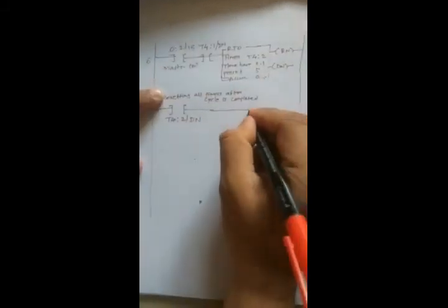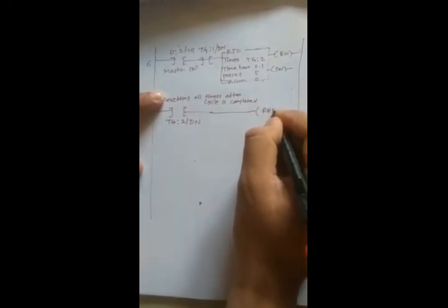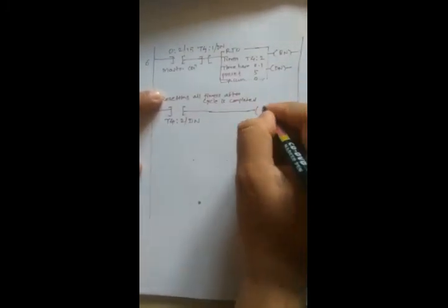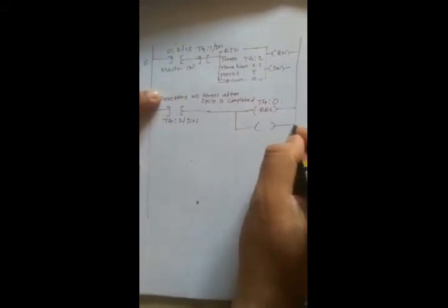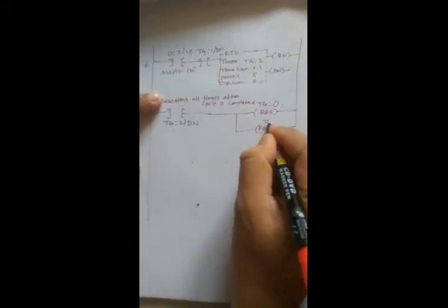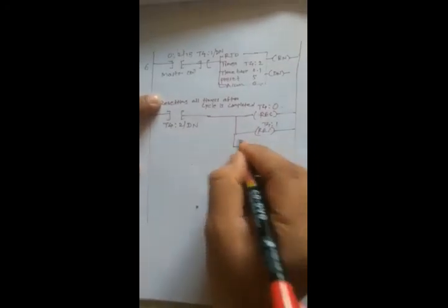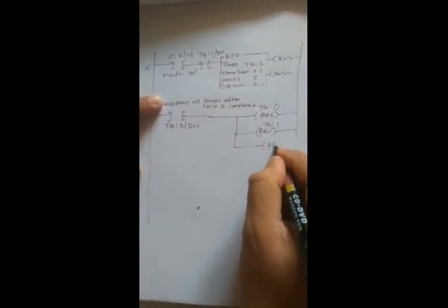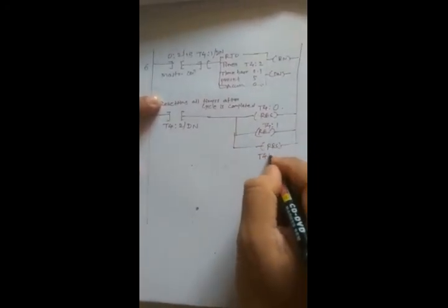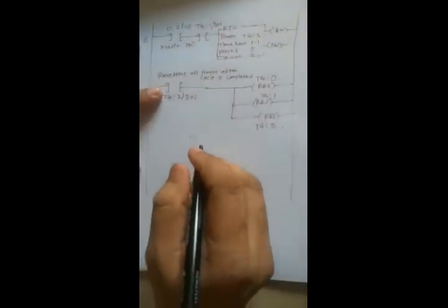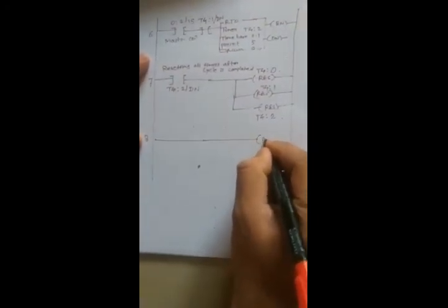So you have to write the additional RES instruction into the coil, and you have to add timer T4:0, again RES for T4:1, and again in parallel RES for T4:2. So in this way you can reset all the timers, and the last rung you will require will be the end of all execution.